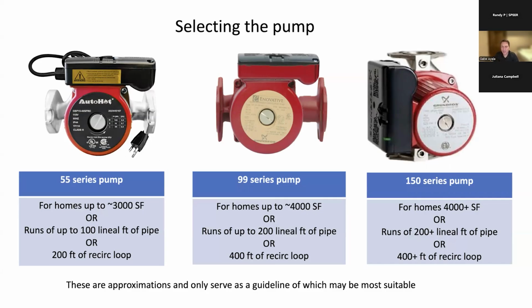And then as you get bigger, to 4 or 5,000 plus square foot homes, you might want to consider sizing the pump up. This is just so that when the loop is being primed and the pump starts activating, it still gets to the end of the plumbing terminal within a reasonable amount of time.